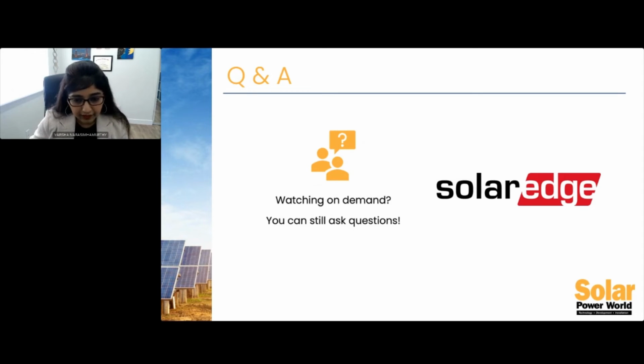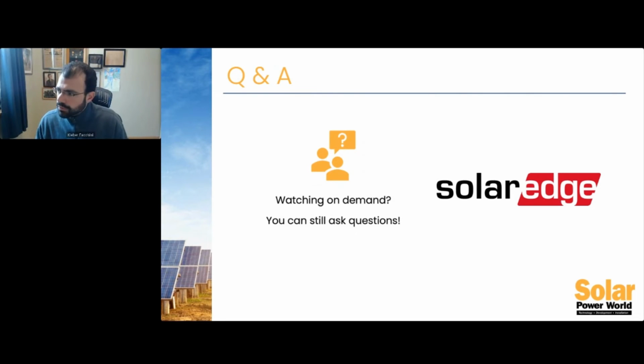Okay, so Clever, a great question is, can the 330 kilowatt inverter be used in rooftop applications where rapid shutdown is required? It's no. So that's a very good question. The inverter cannot be used in rooftop applications because it does not include rapid shutdown. Like I mentioned, it includes the shutdown. It brings voltage within touch safe levels within minutes, but not within 30 seconds. However, this is a good product for carports. So if your carport application allows for 1500 volts DC and there's no rapid shutdown requirement, then this product can be used for carports.